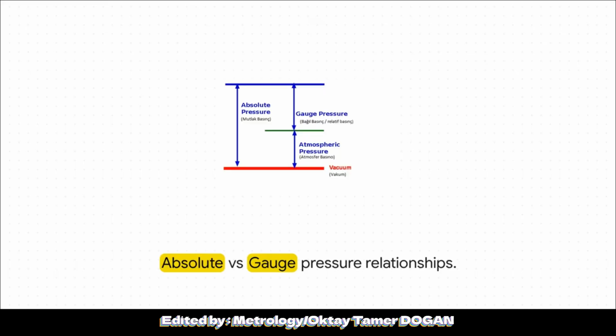Now, you might be wondering how we actually define our 0 point when we measure that force. Well, absolute pressure starts at a true absolute vacuum, meaning literally 0 molecules, 0 pressure. But in the real world of industrial applications, we mostly care about gauge pressure, which is also known as relative pressure. Gauge pressure completely ignores the heavy blanket of the Earth's atmosphere that we're living in. It treats the local atmospheric pressure, which, remember, Torricelli found to be roughly 1,013 millibars at sea level, as its 0 point. So the really crucial takeaway here is that if your industrial gauge reads 1 bar, you actually have to add the local atmospheric pressure to that number to find the true absolute pressure.